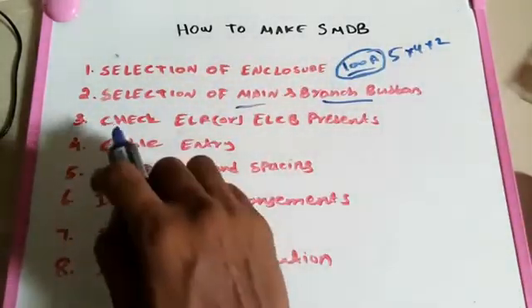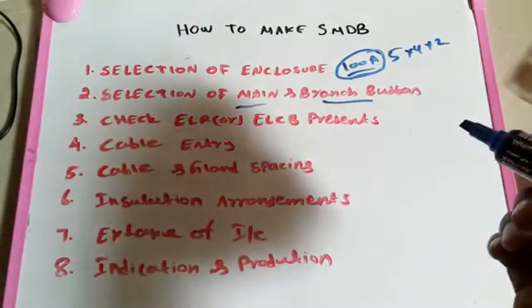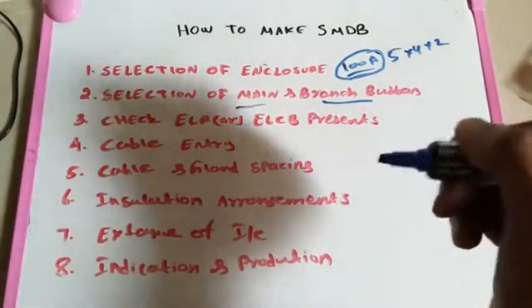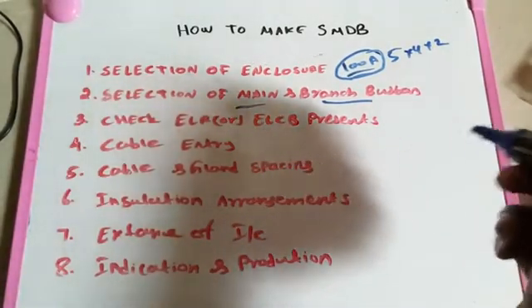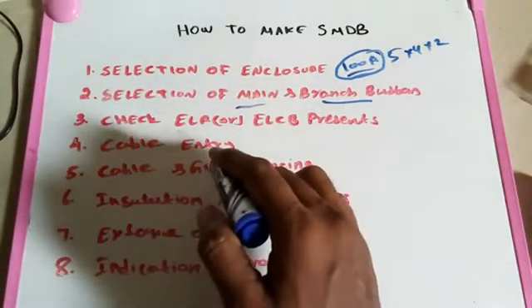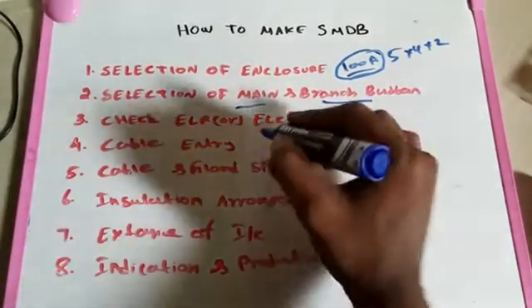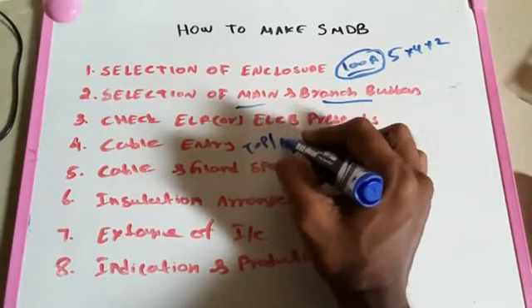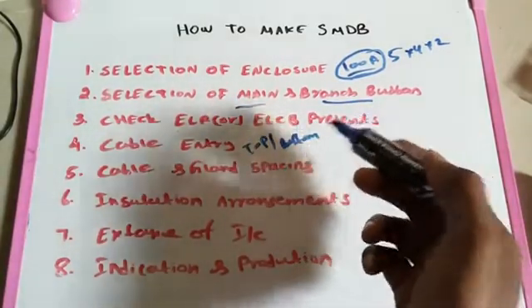Next, check for ELR or ELCB requirements. In this case no ELCB is mentioned, but sometimes it is specified. After that, consider the cable entry — whether the cable enters from the top or the bottom — and construct the SMDB accordingly, as this is a very important consideration.